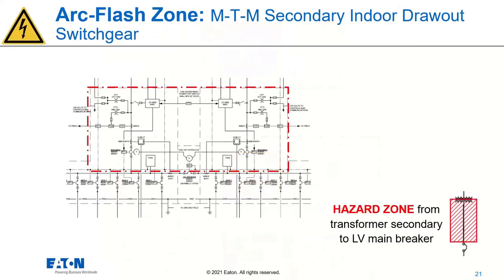So what we're going to look at first is, what if we're just relying on that vacuum recloser? What if it's just that primary protection? And again, this is similar to that poll question. What if I have primary protection alone? I don't have those secondary CTs. I don't have this 50-51 relay. I'm just relying on that vacuum recloser to interrupt whatever fault current, arc flash current I have ahead of my low voltage main in this hazard zone. I've noted it down here, between the transformer and the LV main.